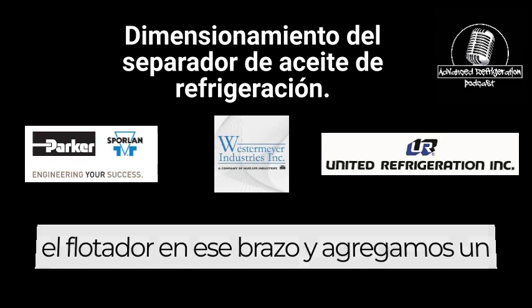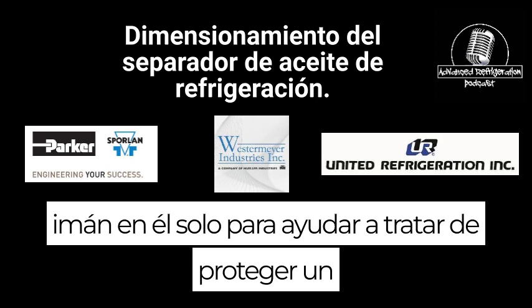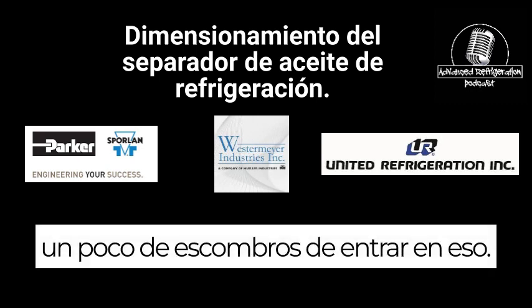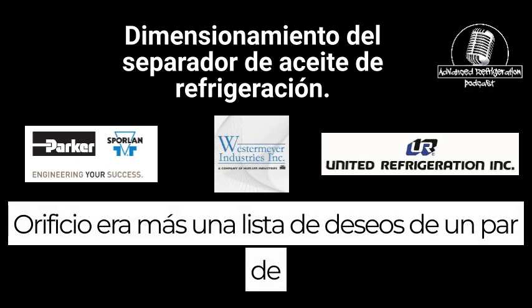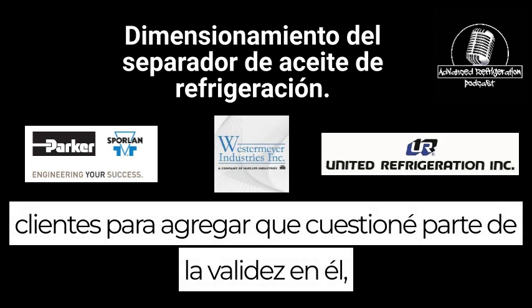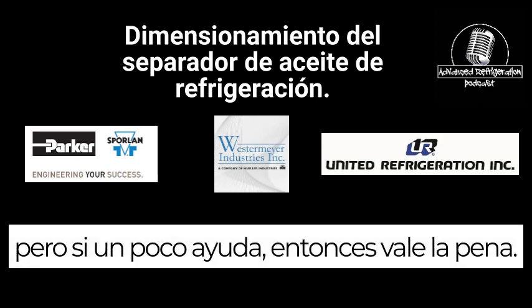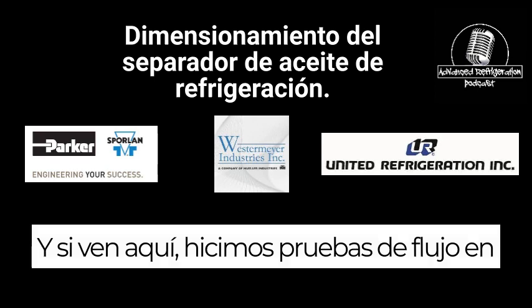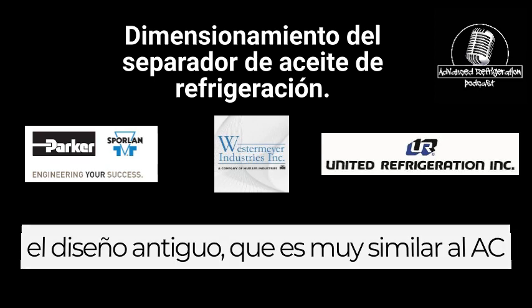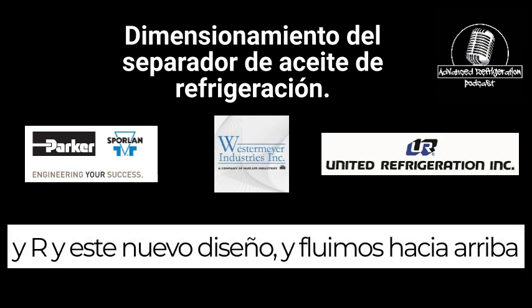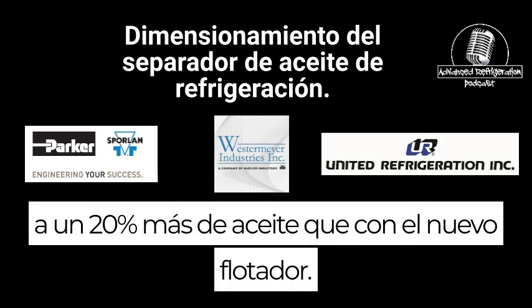We got the float up on that arm, and we added a magnet on it just to help protect a little bit of debris from entering that orifice. It was more of a wish list from a couple customers to add that. I questioned some of the validity on it, but if a little bit helps, then it's worth it. And if you see here, we did flow testing across the old design, which is very similar to the ACNR, and this new design, and we flow up to 20% more oil with the new float.